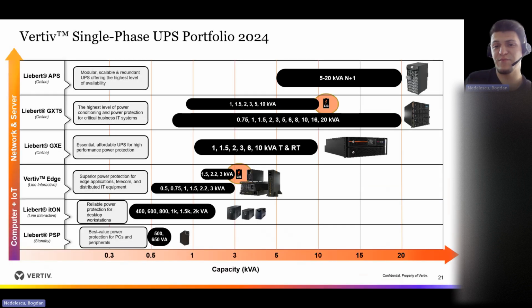And you should know that the UPS product portfolio from Vertiv is divided into two large categories, and these are, as you see in the slide, our single-phase current sources, but we also have three-phase current sources. The main difference between these two categories of products that you must remember are the following. The single-phase sources have a standard supply voltage of 230 volts, and the three-phase ones can be powered up to 400 volts. Also, another differentiation criterion is the power rating. As you see, on the single-phase sources we have a range from 500 VA power up to 20 kVA, while for the three-phase UPS products, we are talking about values starting from 10 kVA and they can reach up to 3,500 kVA.